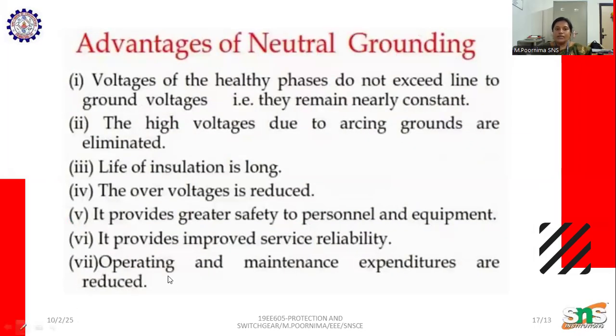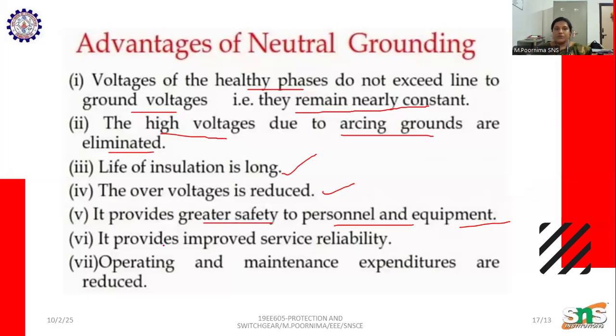So what are the advantages of neutral grounding? The voltage of healthy phases does not exceed the line to ground voltage, that is, they remain nearly constant. The high voltage due to arcing grounds is eliminated. The life of insulation is long. The overvoltage is reduced. It provides greater safety to personnel and equipment. It provides improved service reliability. Operating and maintenance expenditures are reduced. So these are the main advantages of neutral grounding.